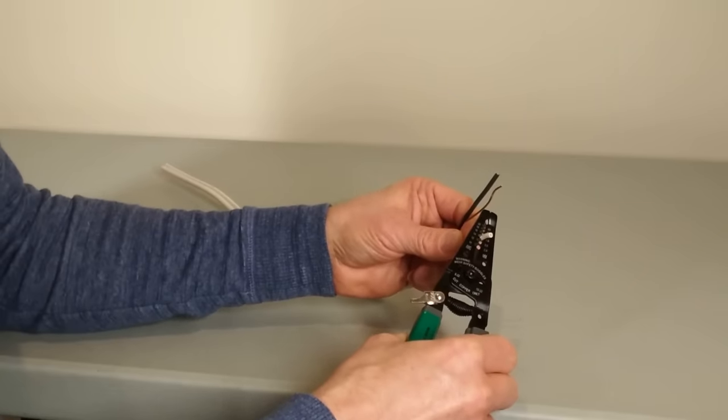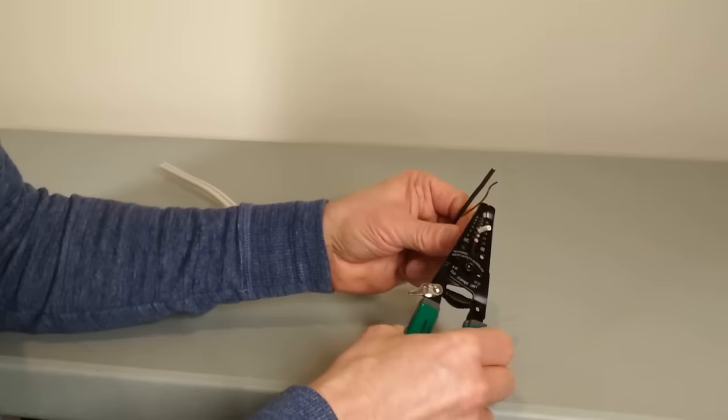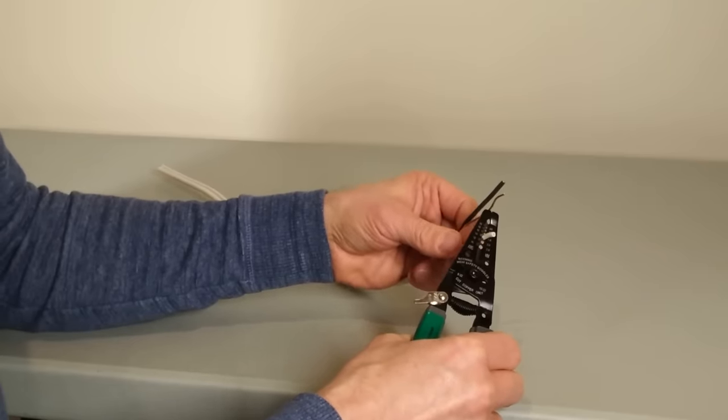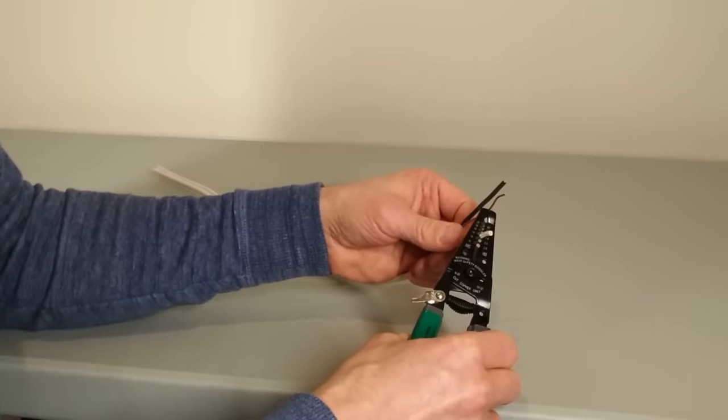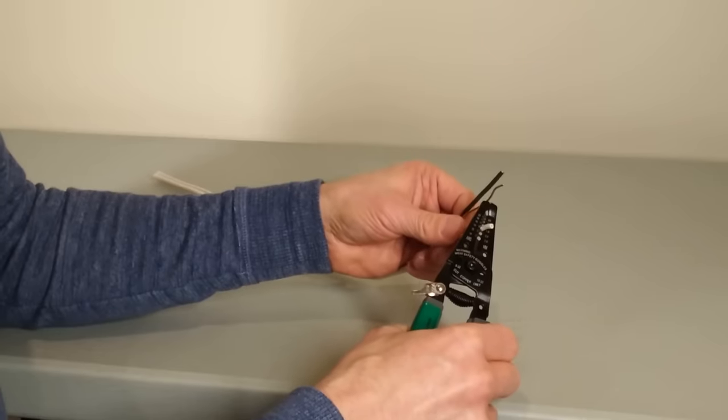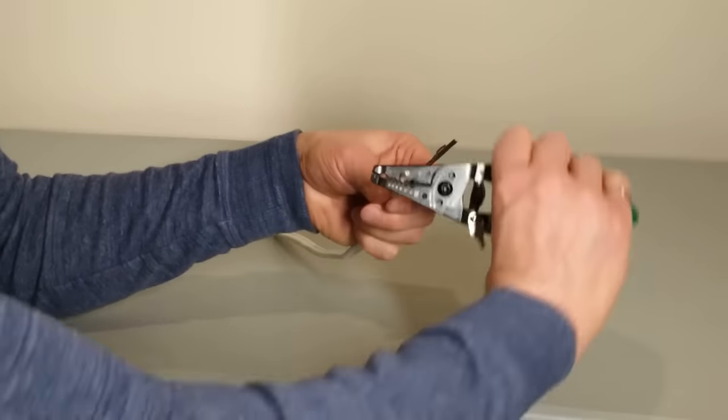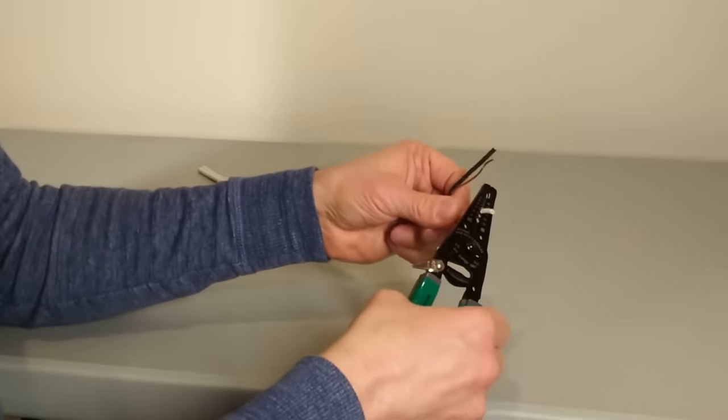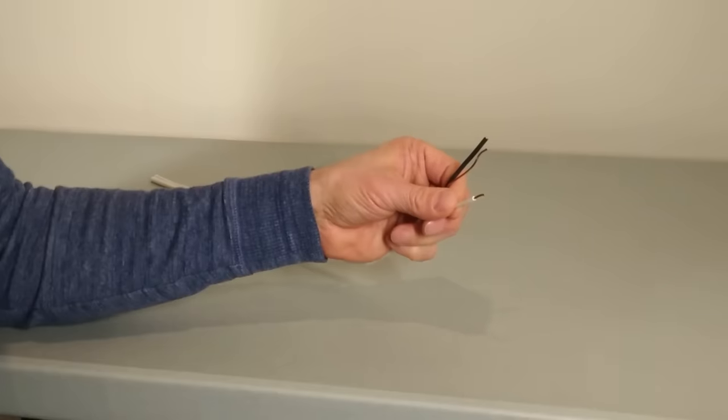Now that may work sometimes, but often it doesn't, like it doesn't here. Why? Because the cutters didn't cut all the insulation all the way around. So best practice is to close the cutters and then quarter turn each way, and then the insulation comes off easily.